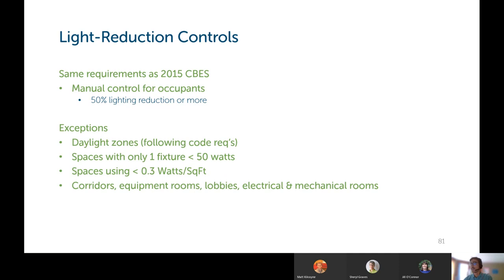Light reduction controls, again, same requirement as the previous code. You need to have manual control in spaces to reduce the light level at least 50%, if not more. Exceptions to this are areas within a daylight zone that are going to be following the daylighting requirements of the code, spaces that have only one fixture that is small, less than 50 watts, spaces that have installed less than 0.3 watts per square foot of lighting power, and corridors, equipment rooms, lobbies, and electrical and mechanical rooms do not need light reduction controls.